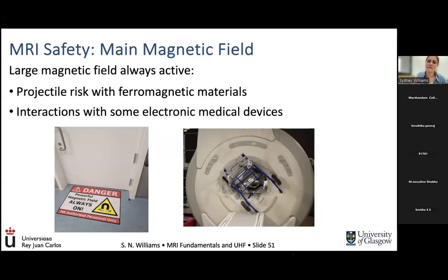In this example on the right, this is a cart that was brought into the MRI scanner room that does have ferromagnetic materials in it and was not approved for MRI. It basically becomes a projectile as soon as it gets close enough to the fringe fields. It will just be projected straight into the center of the magnet, where the field is strongest, or as close as it can get to the center of the magnet. This is a huge accident and it's bad, but fortunately in this case there is nobody inside the scanner. If somebody is inside the scanner, this can very quickly become a deadly experience. So you have to be very, very careful.